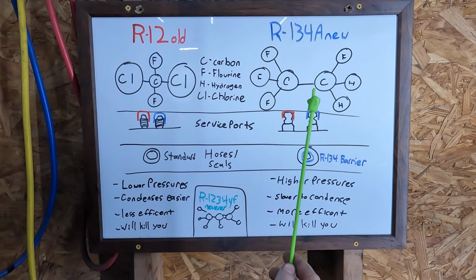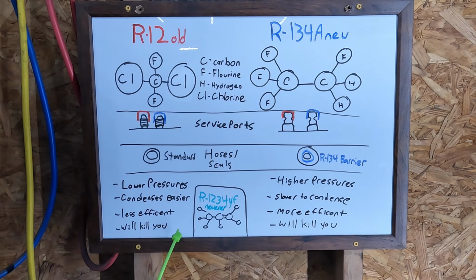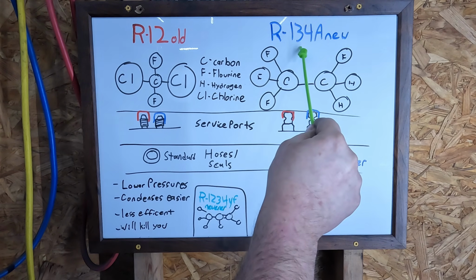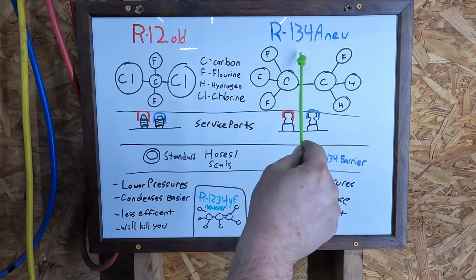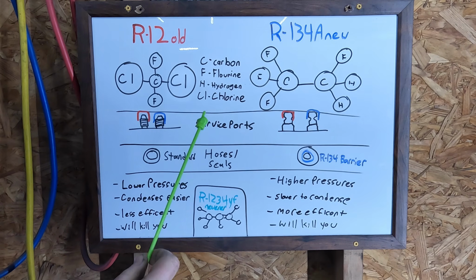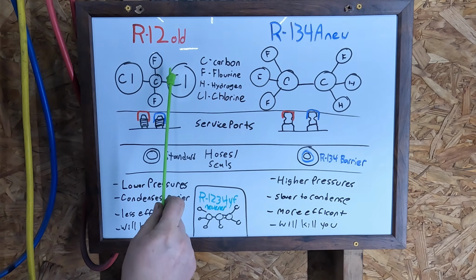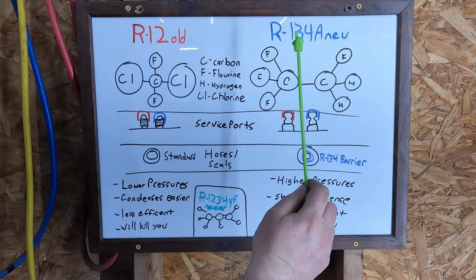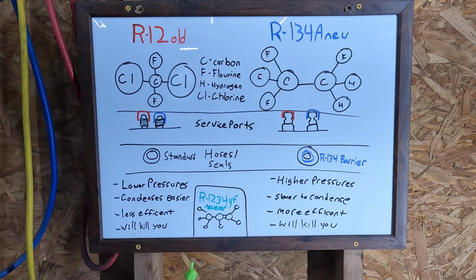Now, a common misconception is that 134 is less efficient than R12. That's not true - pound for pound, R134 is the more efficient substance. It can transfer more heat more quickly. But when you have a system designed to run R12, the system itself can become less efficient with 134a.